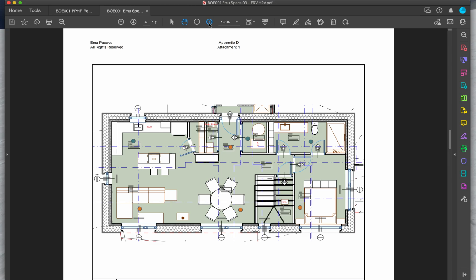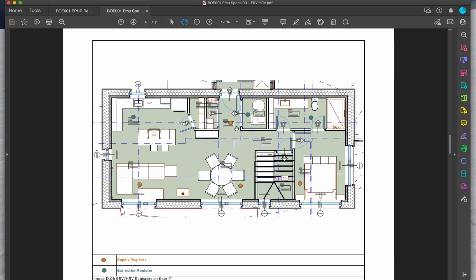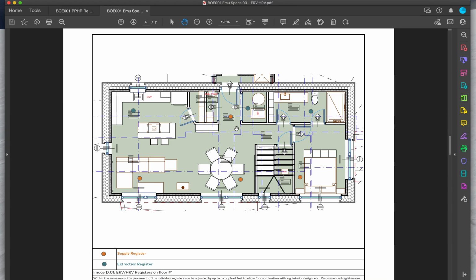Then the next couple of pages are the floor plan of each floor of the building, each floor of the conditioned part of the building. And you see in orange the supply registers, whereas in blue the extraction registers. So we want to supply to the living room, dining room, bedroom, and we want to extract from the kitchen. This is not the kitchen exhaust. Kitchen exhaust is going to be separate. This is something you want to be very clear on. Even in boost mode, a kitchen exhaust register from an ERV or HRV system extracts about 50 cubic feet a minute, which is very little.